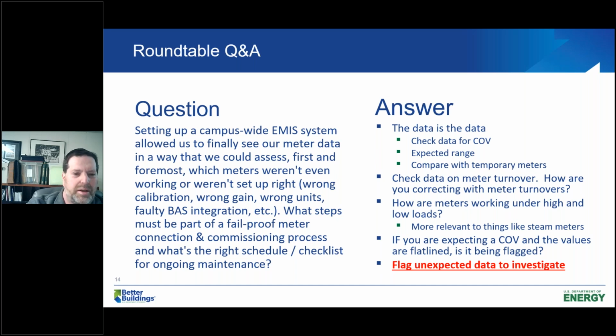Meters always have issues. When they're connected, the key is to check the data for changes. It's not just the initial check, but the changes over time and what the expected values are for calibration. You can compare some with temporary meters also. Meters and all data for that matter need to be checked on an ongoing basis. To accurately indicate what's going on, you have to have ongoing monitoring of the data itself. One of the issues is when meters turn over. Did the meter collection in the EIS or EMIS do a good job with the data correcting when it turned over? If it was going up to 1 million and then turned back to 0, how is it doing that? Is it showing negative results, or does it know what it's doing? We have daylight savings time coming this weekend. Does your EMIS know what to do with that 1 hour difference?